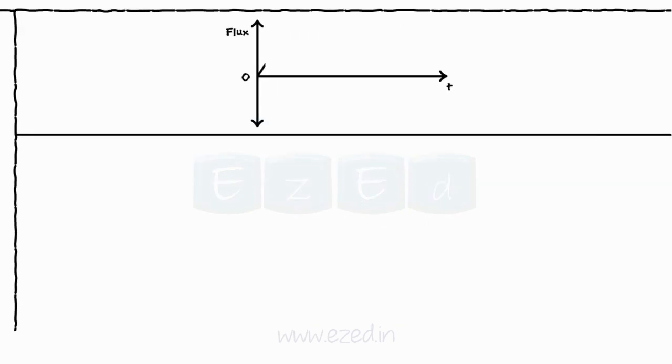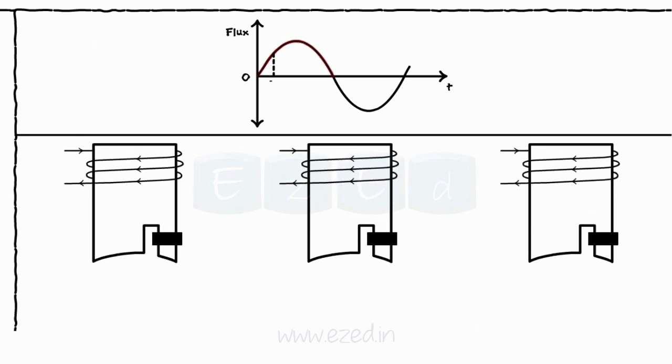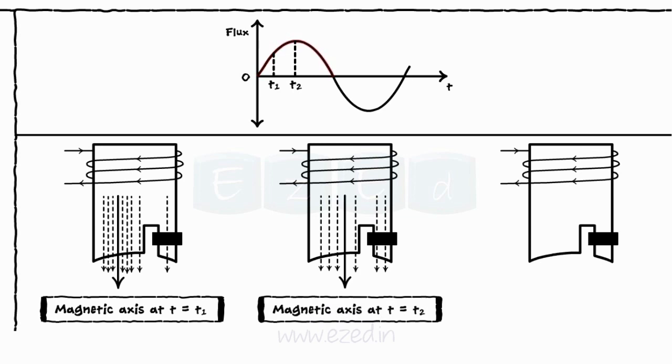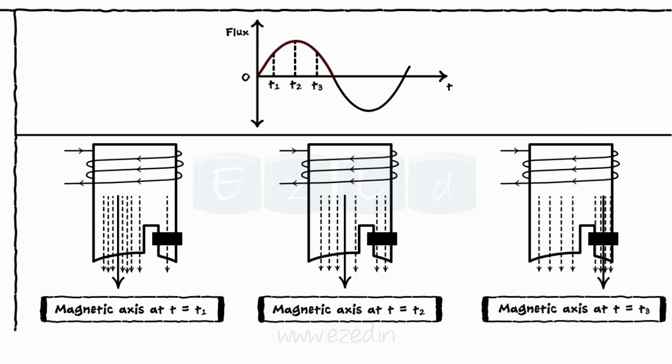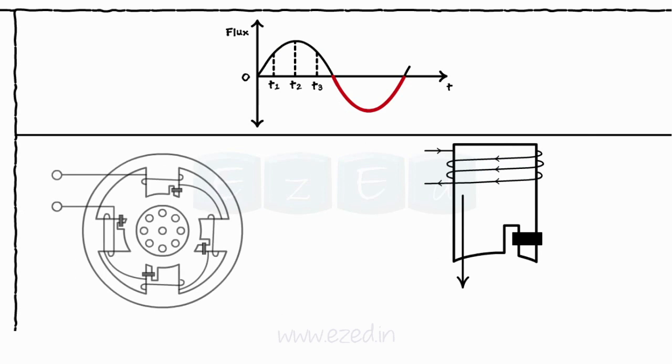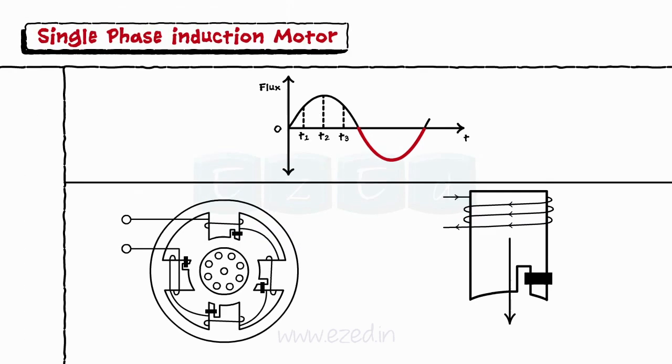As an AC signal is applied to the motor, the magnetic field gets generated. As the magnitude of the AC signal increases in the first half, the magnetic axis shifts from the non-shaded area to the shaded area and back to the non-shaded area. The same motion of axis happens during the negative half also. This motion of axis exhibits the nature of rotational magnetic field and motor starts to work immediately.